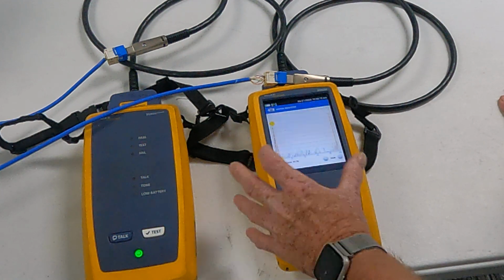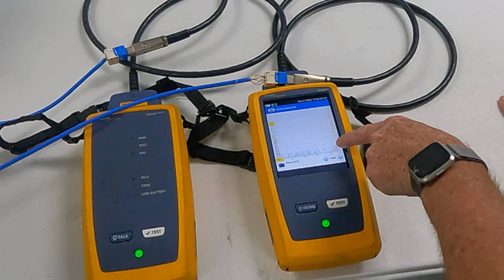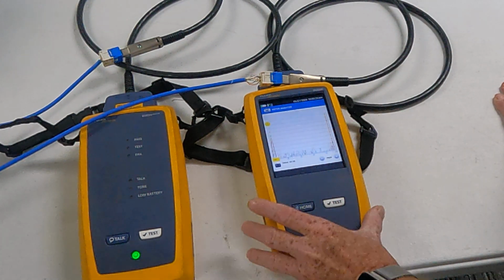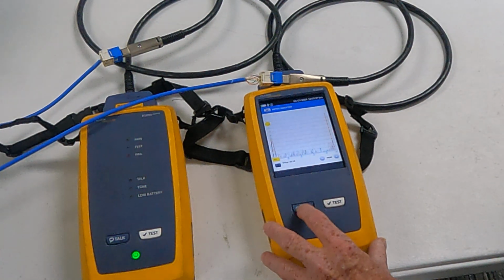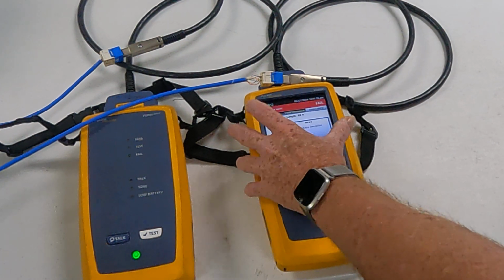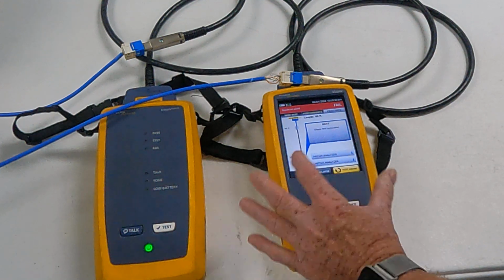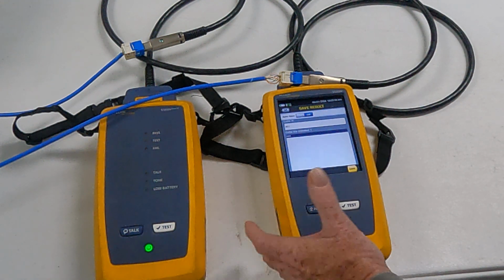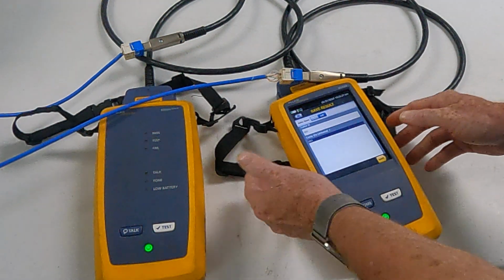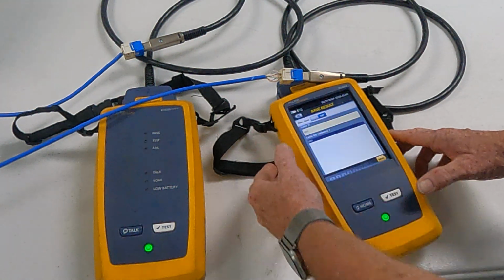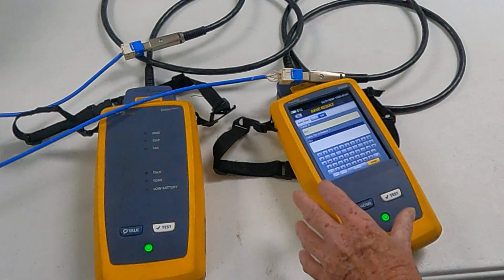Okay, you can go into the analyzer and it'll actually show you where it's failing and what end and how far in and where the worst value margin is. So going back, if you don't have time right now, you can just push fix later, okay? And then you want to just document what the number is. Now make sure that you put the right cable ID in there.